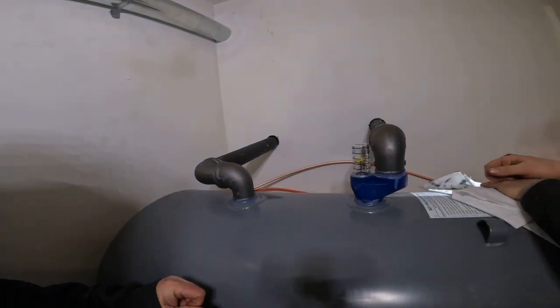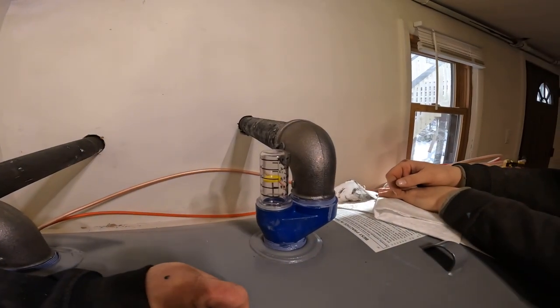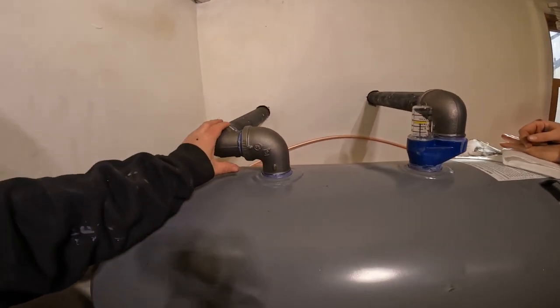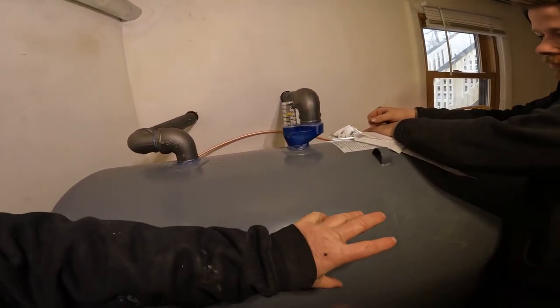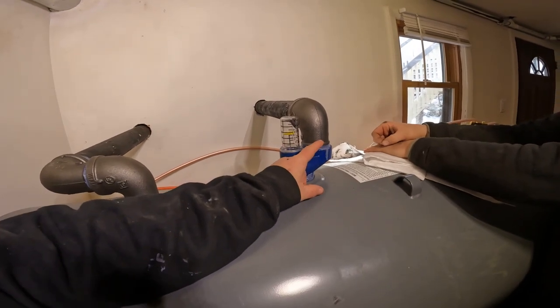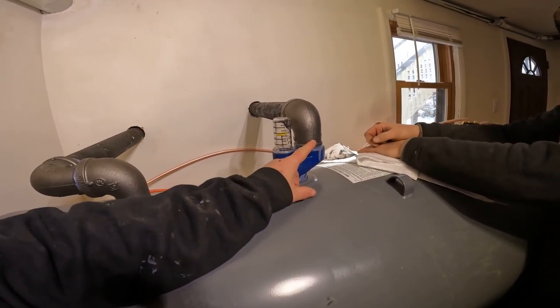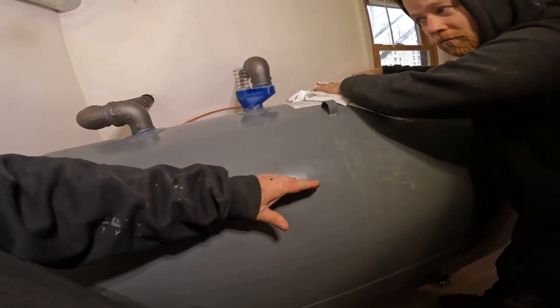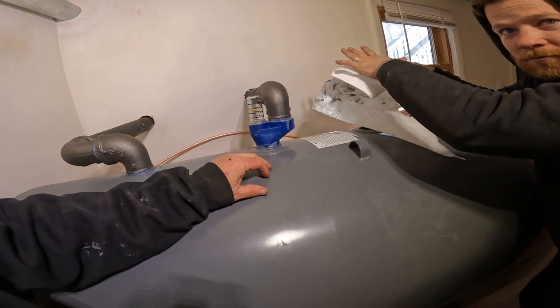Love the cold weather. Okay, progress. The pump is unfrozen and we are now filling. I don't know if you can hear that vent. It's whistling. It's a whistle vent. As the oil comes in, it fills up the tank. The air has to excrete out. There's a whistle in there. The reason is that once the tank gets to 95% capacity, the whistle shuts off.